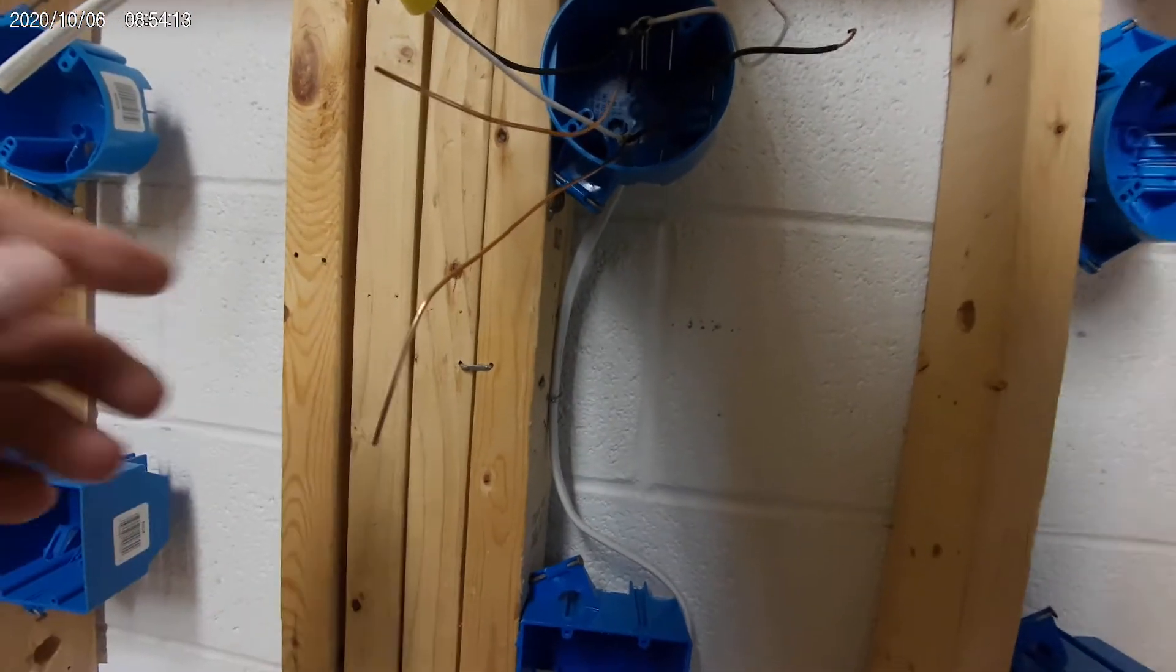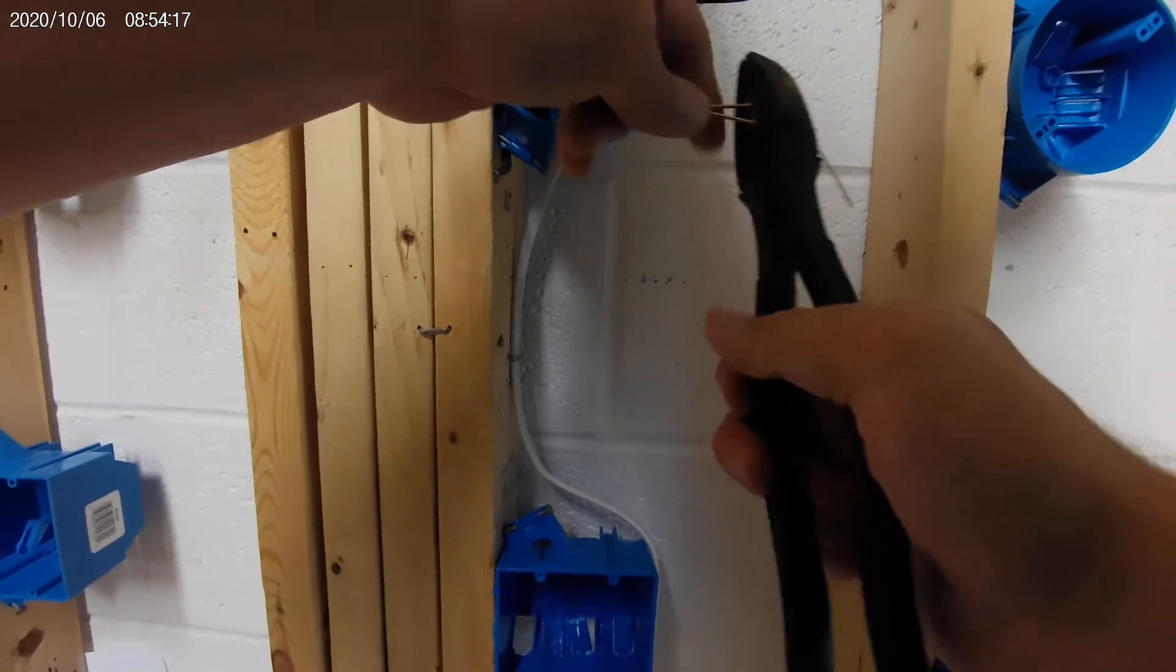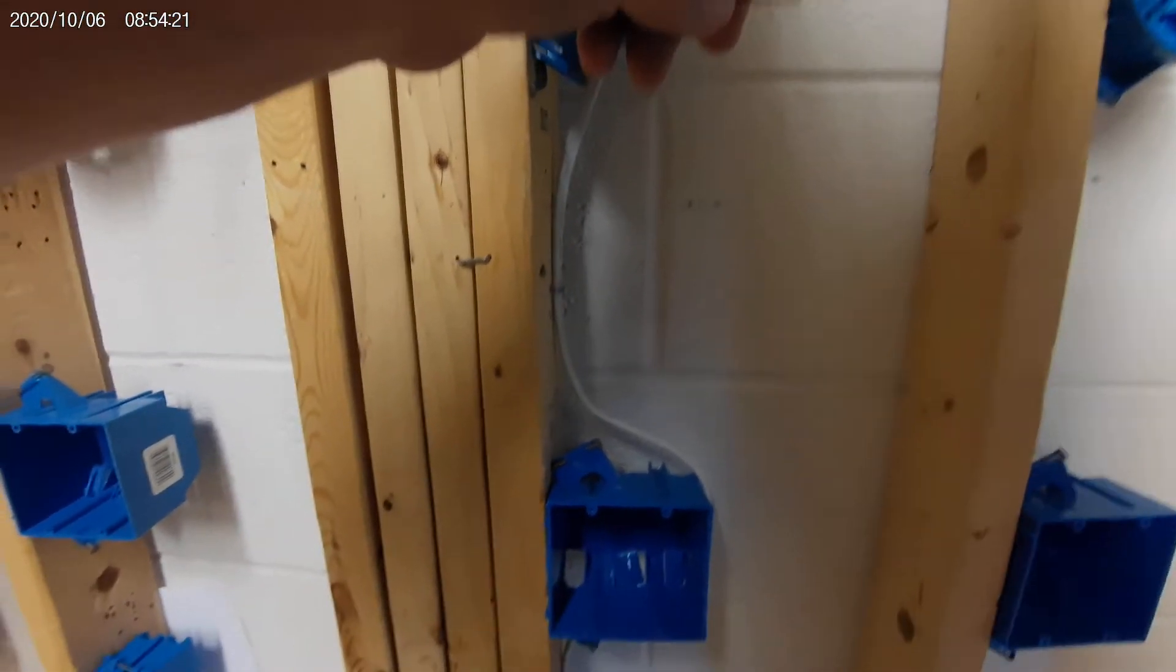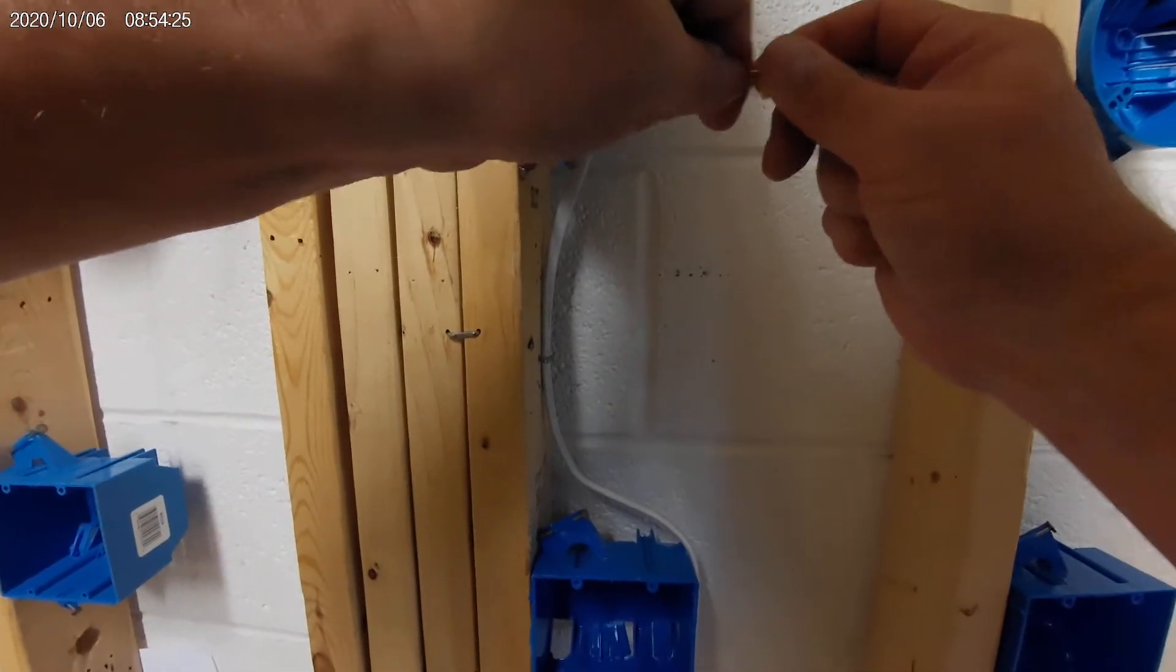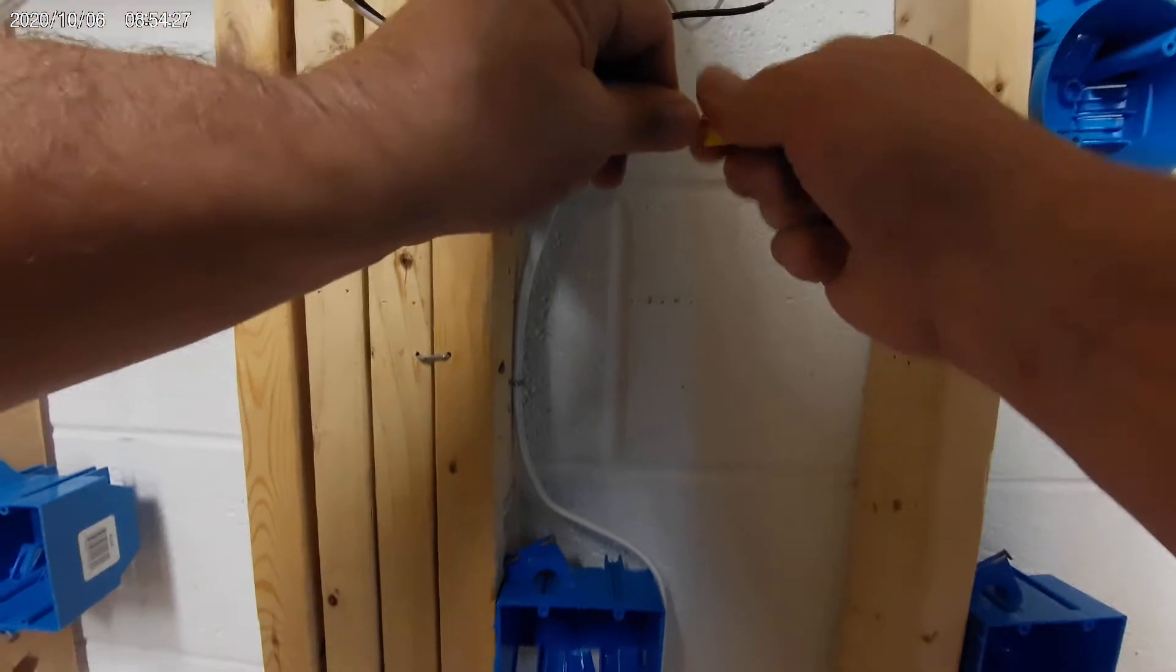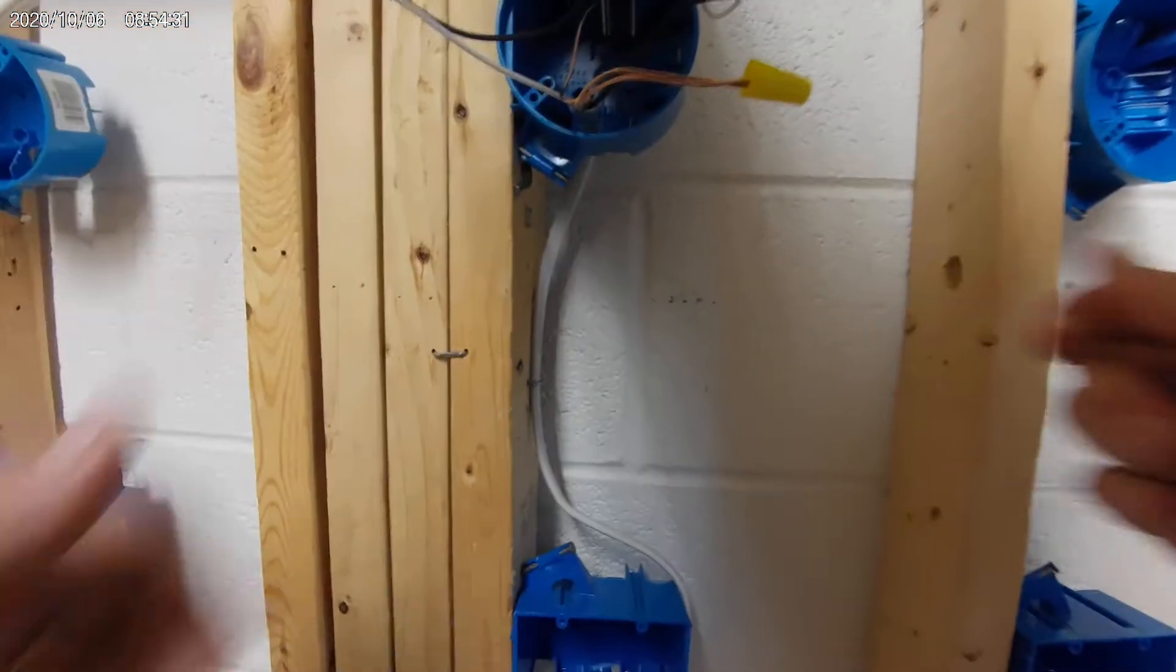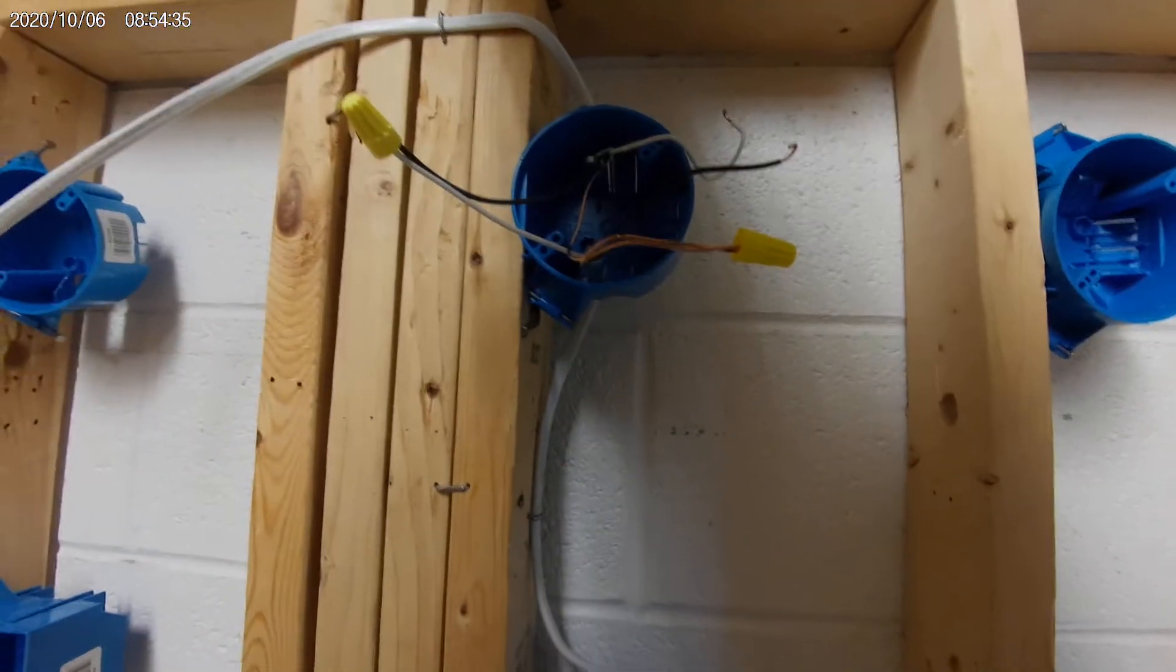The purpose of the ground is for the non-current parts, metal parts of a fixture. Since there is no metal, there is nothing to ground. So what we will do is take the grounds and just wire nut them off. We don't cut them out because what if in the future someone comes on with a fixture that does have metal parts, then it needs to be grounded.